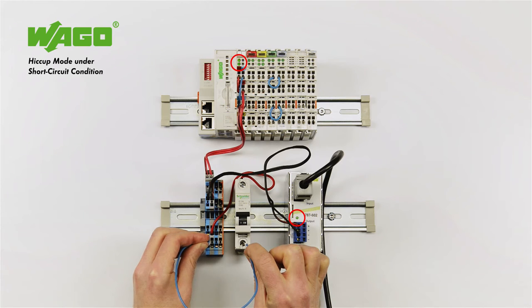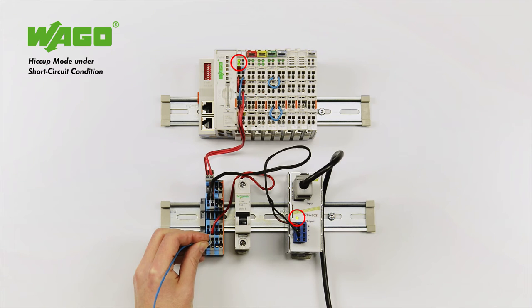As the short circuit current is repeatedly interrupted by the pulsating deactivation of the output, the miniature circuit breaker will never trip. The magnetic trip unit is not triggered, as there is no high short circuit current present. Due to the pulsating deactivation, the conductor does not heat up, meaning that the thermal section of the fuse does not respond. If the short circuit was detected and eliminated now, there would be the risk of the machine automatically starting up.